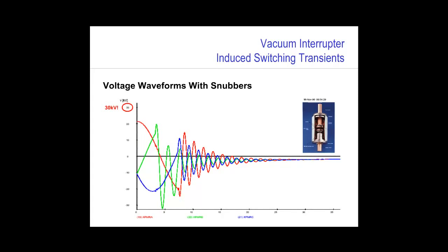We can install a resistor capacitor snubber network on the output of the vacuum circuit interrupter, which will reduce the voltage transients that occur when the VI opens. In this case, I've brought the transients down to 30 kV, which is well within the rating of the transformer. It's interesting to note here that this issue is really directly linked to the proximity of the vacuum interrupter to the transformer inductive load. As I add resistance, either in cable impedance or, if I was interrupting a fault, impedance across an arc, then that will effectively reduce the voltage spikes that will be seen when the VI opens.